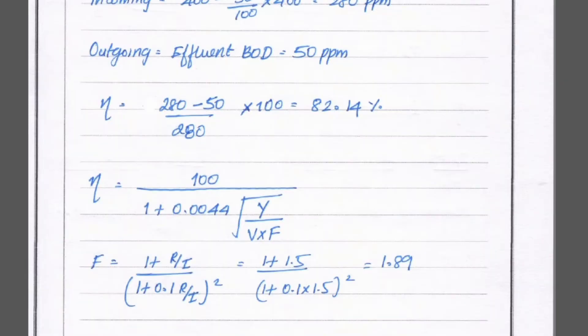The outgoing BOD is given as 50 ppm. So efficiency = (280 - 50) / 280 × 100 = 82.14%. Now we apply the NRC formula: efficiency = 100 / (1 + 0.0044 × √(y / (v × f))), where y is BOD in kg/day, v is volume, and f is the recirculation factor.